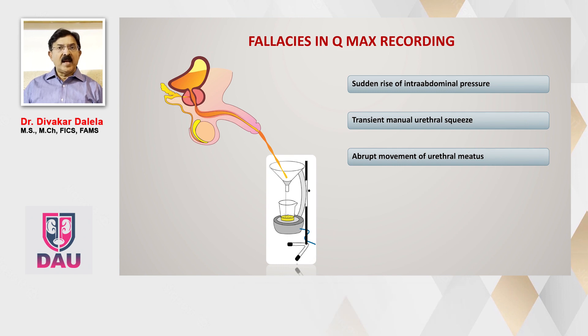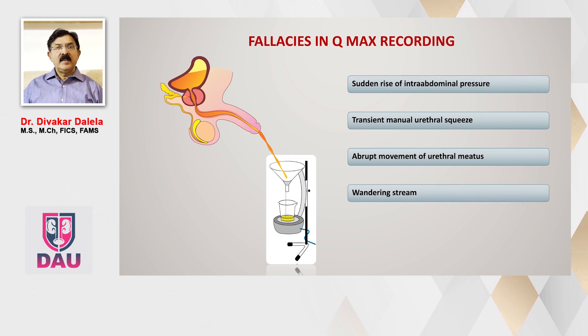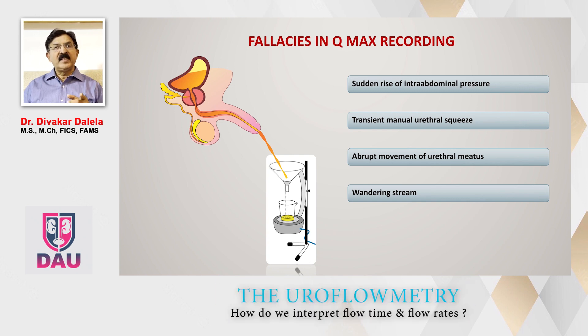There can also be an abrupt movement of the urethral meatus by the patient, which changes the speed of fall of the stream in the funnel. Some patients wander their stream all around the entire funnel of the flowmeter. We should tell the patient beforehand not to do so, but if they do, this wandering stream can also have an impact on Q-max.